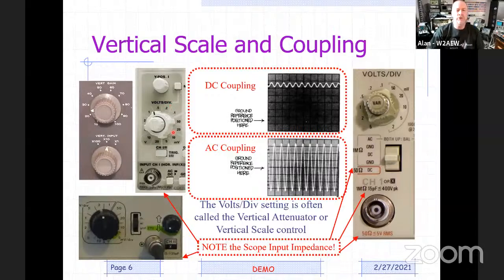Some of the older service scopes you might find, and I'd say steer away from, are these uncalibrated scopes where you just have an adjustable vertical attenuator and a vernier control. They're good for looking at relative amplitude waveforms, and you could put a known amplitude in and adjust things to get a calibrated reading, but these days there's almost no reason to use those because you can get good calibrated vertical scales on scopes pretty easily.